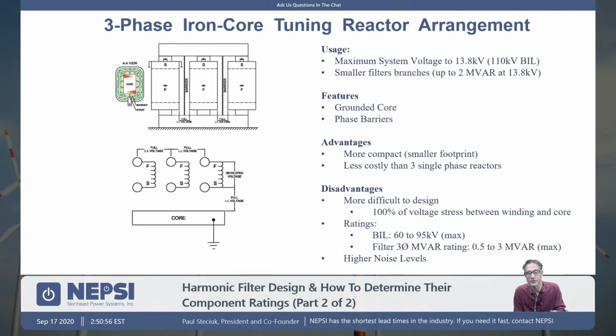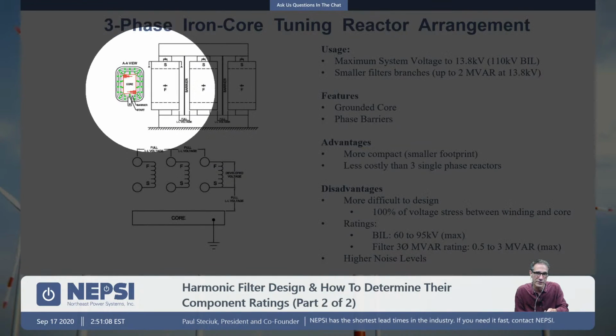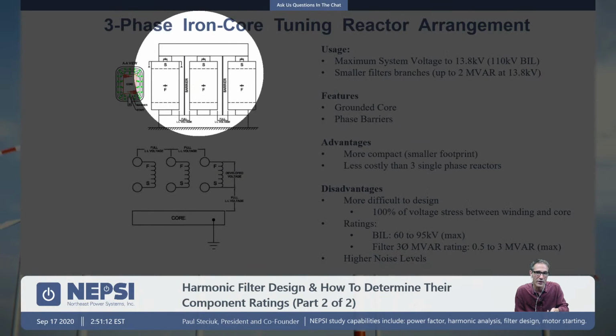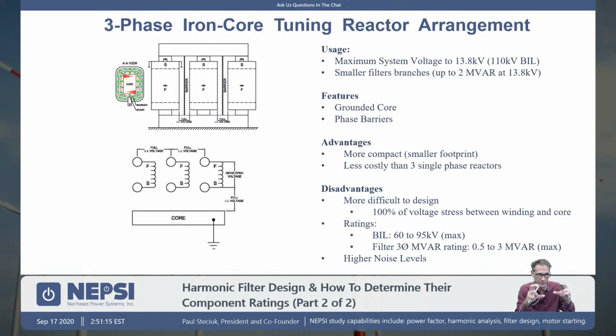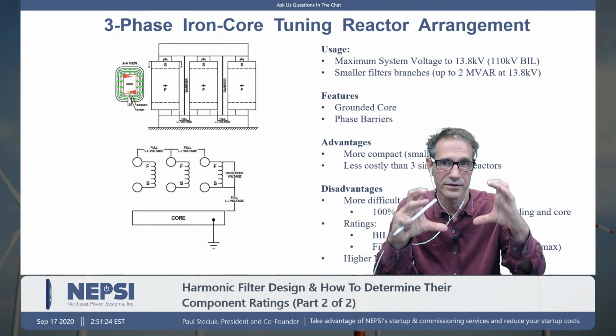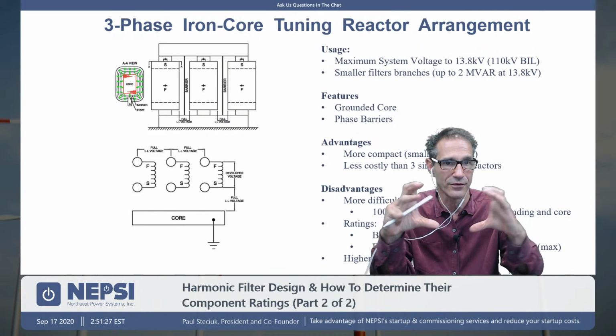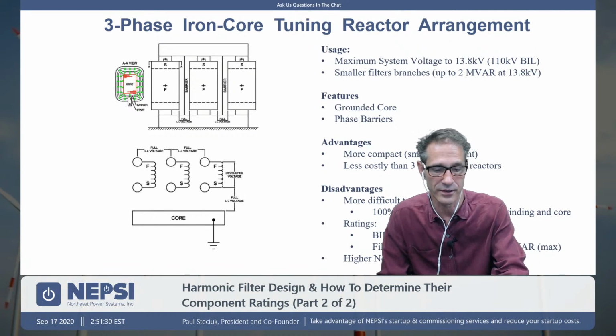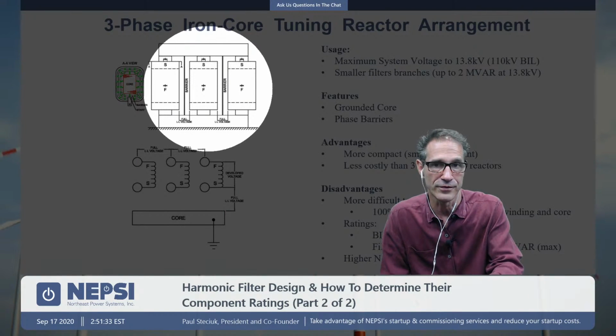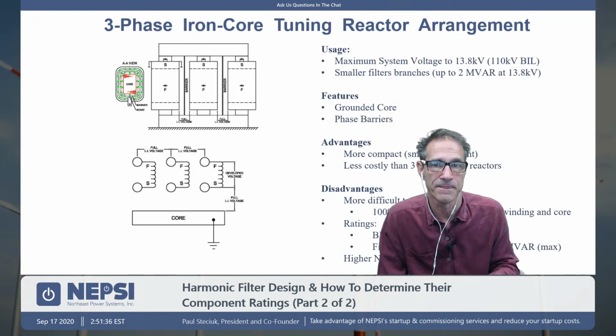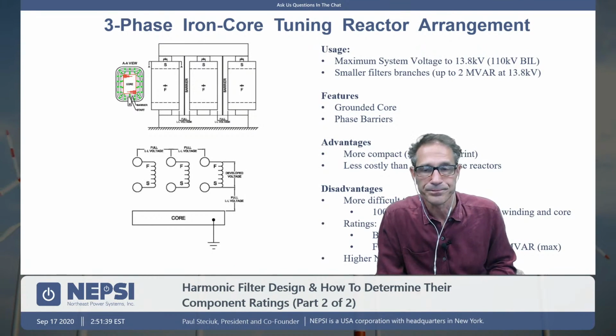There are some disadvantages associated with this 3-phase reactor. One is that it's difficult to design the reactor to not be noisy. The design process is much more critical, because we're sandwiching the gaps within each of these legs, and the tolerance must be kept very tight between phase A, B, and C. So when they clamp the core, the pressure within the core structure must be about equal. If it's unequal, you can get a set of laminations, say in the middle leg here, where we don't have even clamping force because of the tolerances within the gap structure, and we can get a louder noise. So that's the one thing.